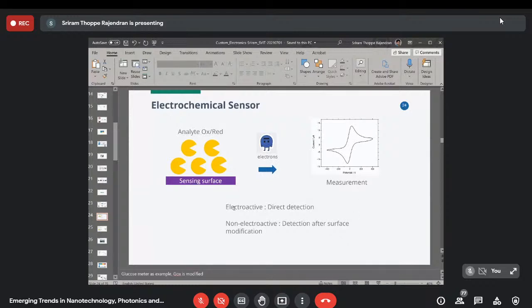So if the analyte you're measuring can directly oxidize or reduce, then it is called an electroactive analyte. That's the term here. And then there are some analytes which do not directly do this. You need an intermediate step for this electron transfer to occur. And in that case, rightly, it's called non-electroactive because it needs more processing.